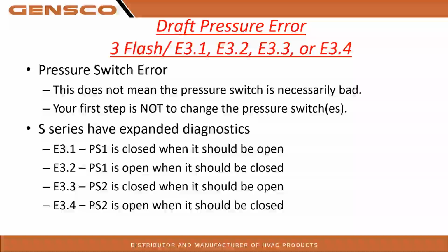So pressure switches, guys, hardly ever fail. I think I've only ever really replaced 2 in my career. And I've had a pretty long career. So very, very rare. Usually the first thing that gets blamed when there's a pressure switch problem, but typically not the problem. Okay. So we're going to want to investigate why. Don't change the pressure switch right off the bat. We need to actually investigate why.